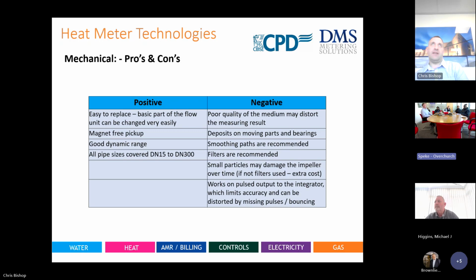Filters are recommended, and that's in relation to a water profile. Cold water filtration is important because it's WRAS approval. Hot water is obviously relevant for filters as well. It's more cost. You have to do more design and more straight lengths of pipe. Plant rooms are getting a lot smaller nowadays, not bigger, so that's a challenge to pass on to yourselves to get right. And again, small particles can damage the actual meter, and that can cause replacements to happen.